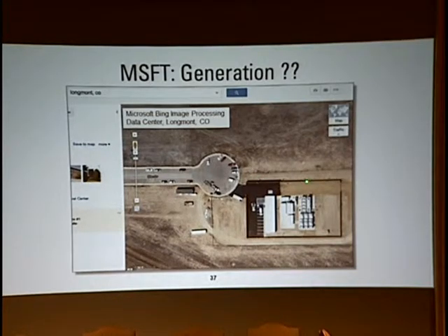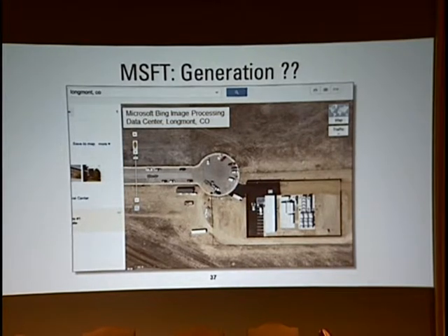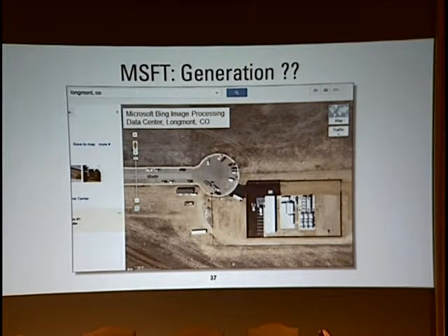This is a cinder block screen wall that's the only construction, and then this is a steel building, a pre-assembled steel building that they put offices in. So very low overhead, very low cost. They're going to build out 5 acres of this stuff, 5 megawatts, and they're living the dream, right? Free cooling 100% of the time. They don't have chilled water anywhere in there. They just run these things like crazy.